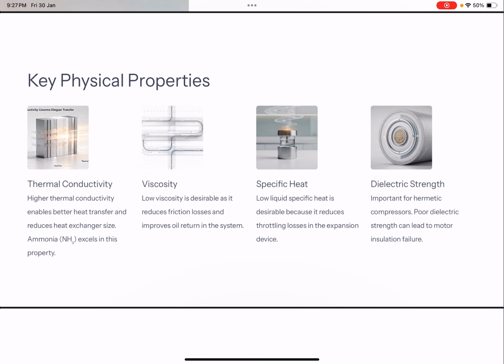Now, how is that so? For that, you need to be clear on the representation of the cycle on the pressure enthalpy chart, because a lower liquid specific heat means the heat required to change the temperature of the condensate is less. Liquid means condensate, because liquid in the vapor compression system is obtained after condensation. So if you have a low liquid specific heat, then your throttling losses would be reduced in the expansion devices. Dielectric strength is another important property, especially for hermetically sealed compressors. If there is poor dielectric strength, that would lead to the failure of the motor insulation.